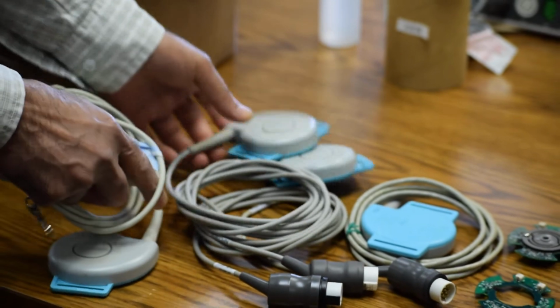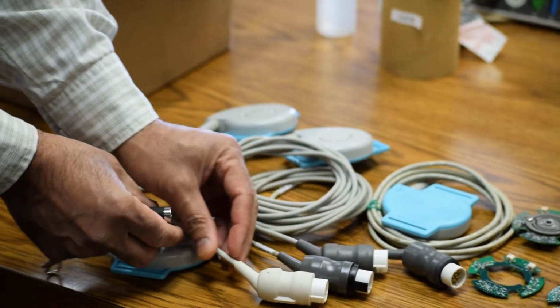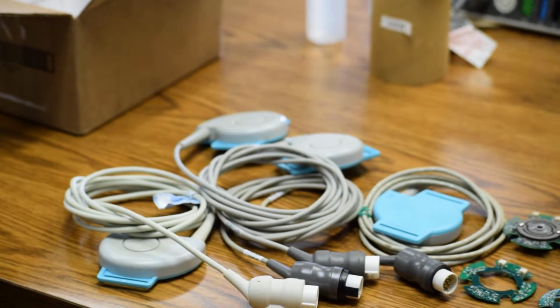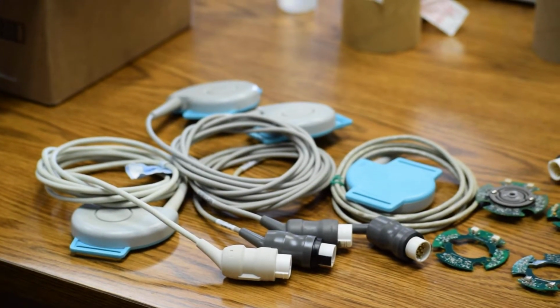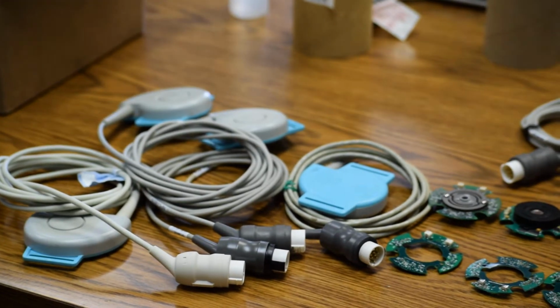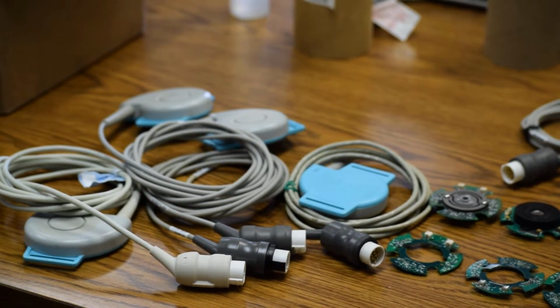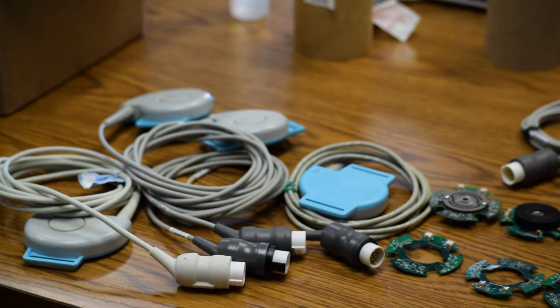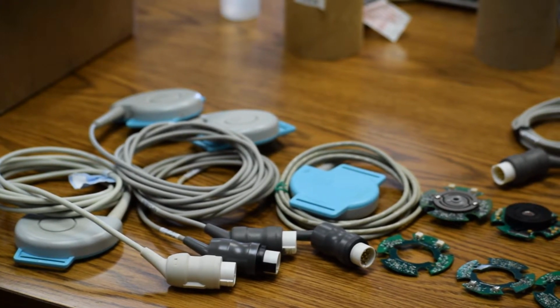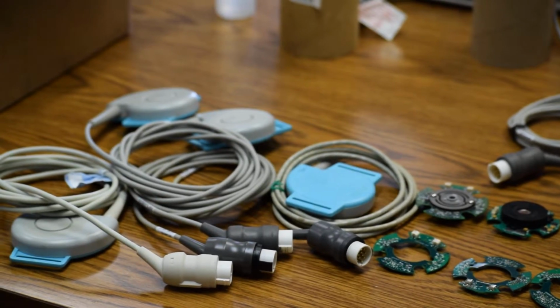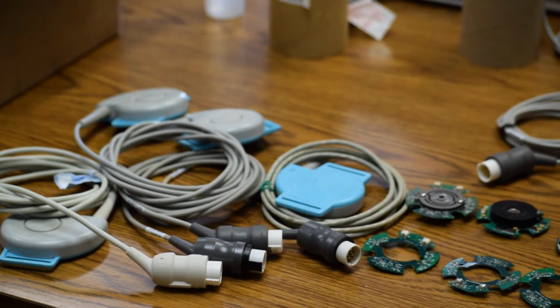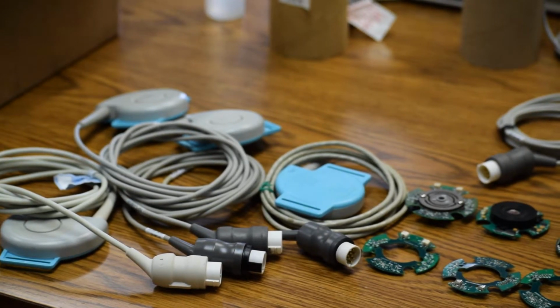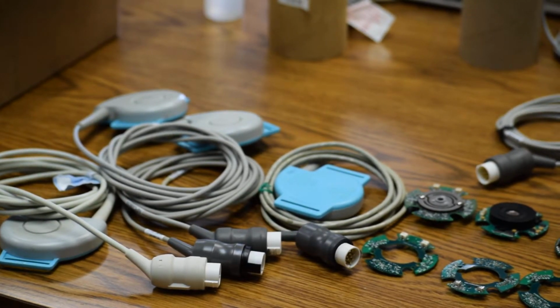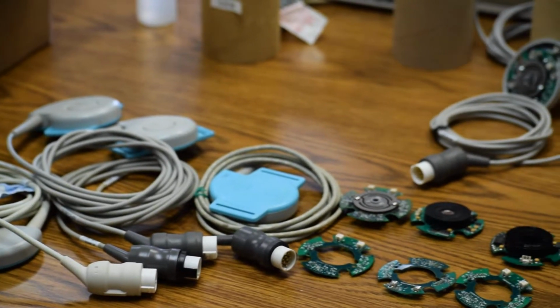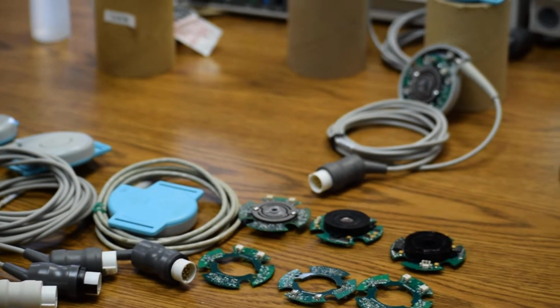Let us put them together. The biomedical engineering manager reported repeated failures and extremely poor performance of Toco tracing with baseline drift. The one transducer that is original with a GE factory serial number can be 100% brought back to the original specifications by repairing at component level, within plus or minus 2 Toco counts for baseline stability.